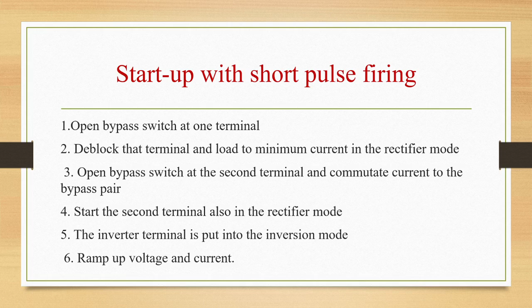First one is open bypass switch at one terminal. Second is deblock the terminal and load to minimum current in the rectifier mode. Third is open bypass switch at the second terminal and commutate current to the bypass pair. Fourth is start the second terminal also in the rectifier mode. Fifth is inverter terminal is put into the inversion mode. Sixth is ramp up voltage and current.